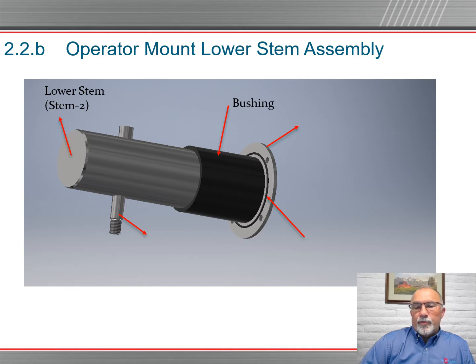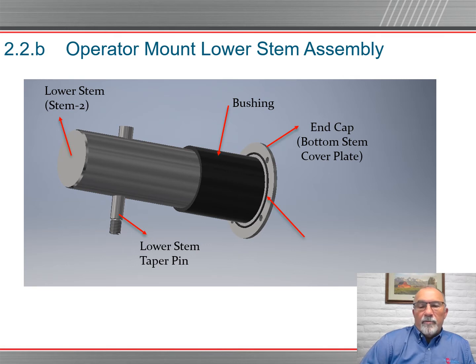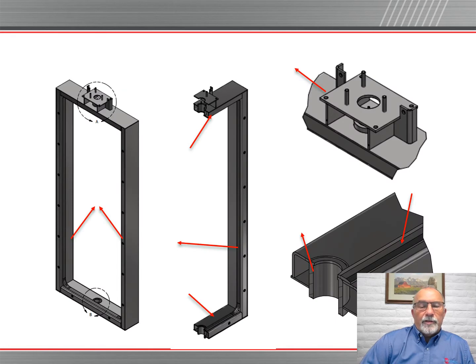Shows the lower stem, which was referred to previously as stem number 2, and of course the bushing and the end cap bottom stem cover plate. This is at the very bottom of the valve, and that cover plate prevents any debris from entering our pin area. The lower stem is a tapered pin that's actually connected to the vane or cover. There's your O-ring for seal.